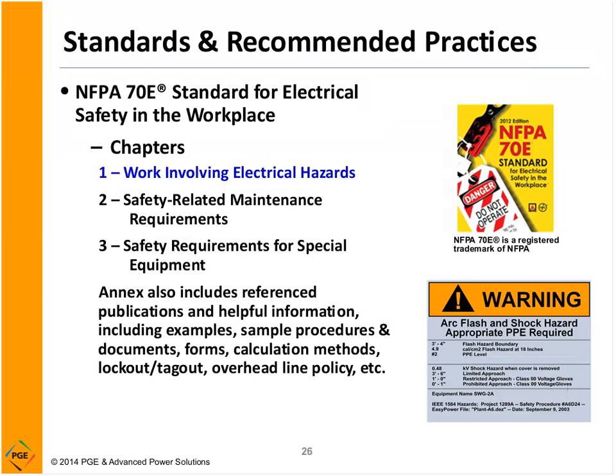We also have in the industry NFPA 70E, Standard for Electrical Safety in the Workplace. We're going to touch on a few elements out of Chapter 1, work involving electrical hazards, but this is a reference that OSHA uses. A lot of folks in the industry use the NFPA, National Fire Protection Association, 70E, the Standard for Electrical Safety in the Workplace. OSHA also references this document. They don't mandate that you use 70E, but they reference this document in providing information that could be helpful in complying with the OSHA requirements for electrical safety. Now, the annex in this document also includes reference publications, helpful information, examples, sample procedures, documents, etc. If you do not have a copy of this, I would highly recommend going to nfpa.org and downloading a copy of that. Of course, it is for sale. You can access it to review online, but if you want a copy for your own use to review and to print out, you do have to purchase that document.